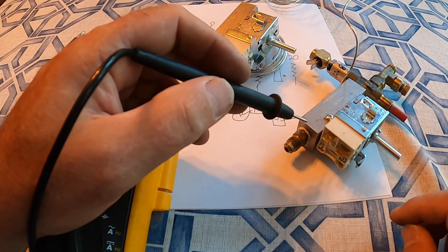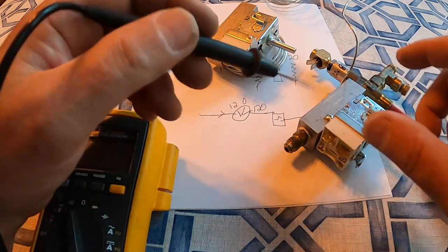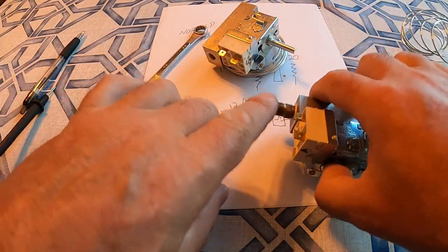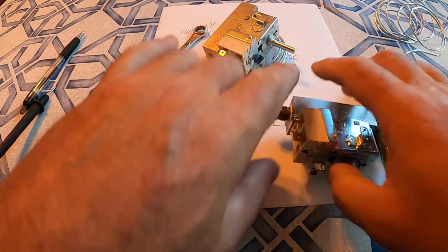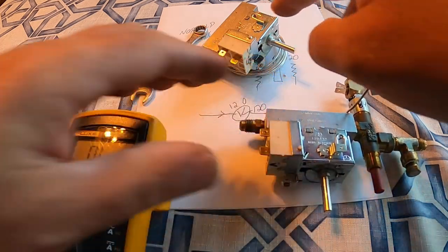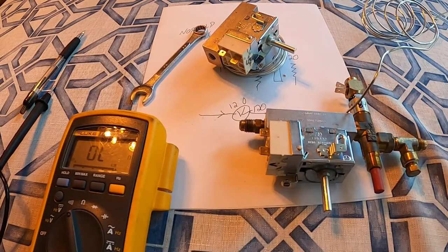So this guy is trying to tell the heater to come on. As it should be. And this guy. Nothing. So that switch that's inside there is bad. So what we're going to do is spin this guy off. Spin this assembly off and put it on there just like it is now.